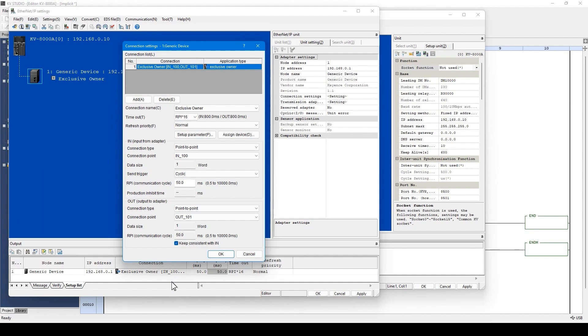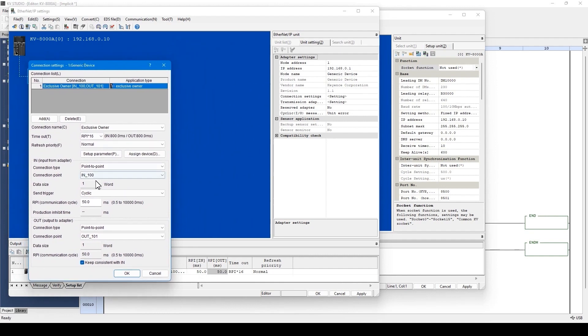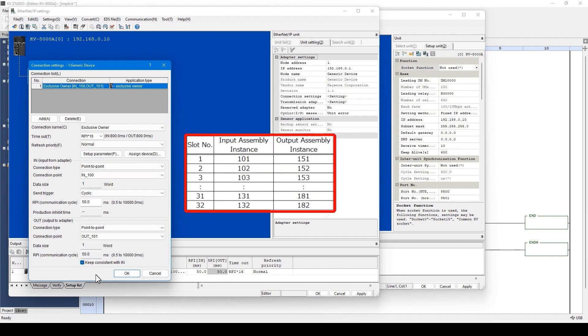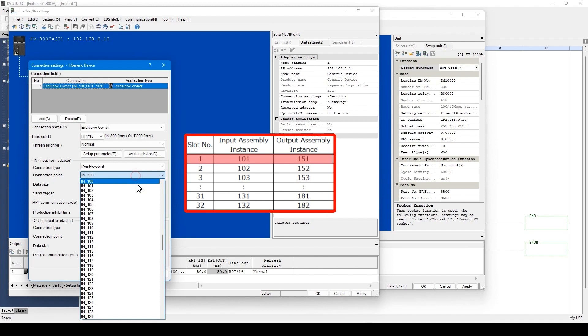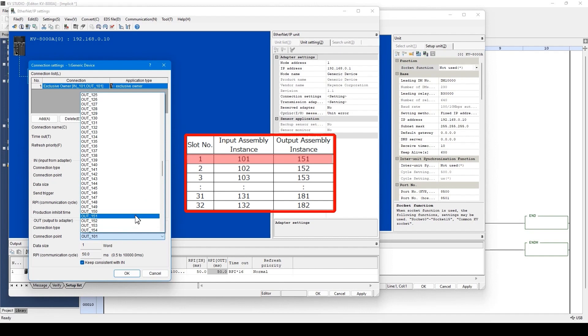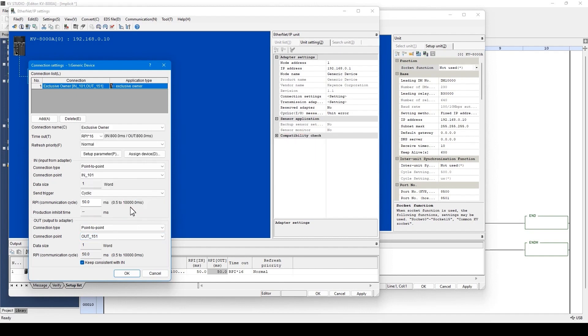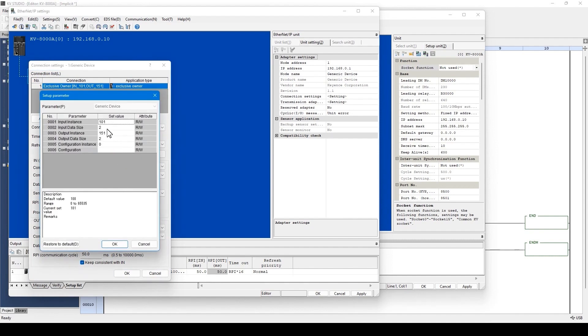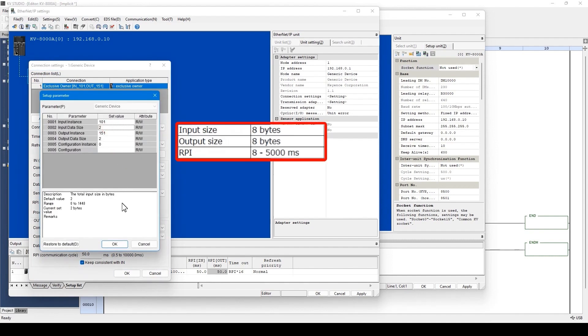Refer to the manual of the device for the necessary settings information. Set the connection point. According to the manual, these are the connection points. All data to communicate with the robot is assigned to slot 1. Select input 101 for the connection from the robot to the PLC, and select output 151 for the connection from the PLC to the robot. I need to set the data size. According to the manual, I need to have 8 bytes for each word.